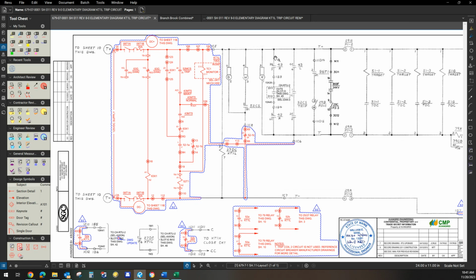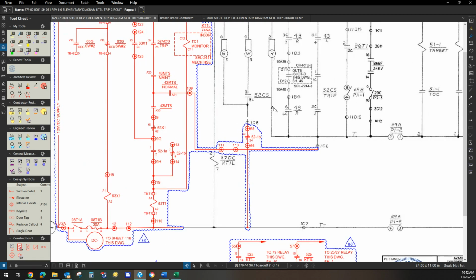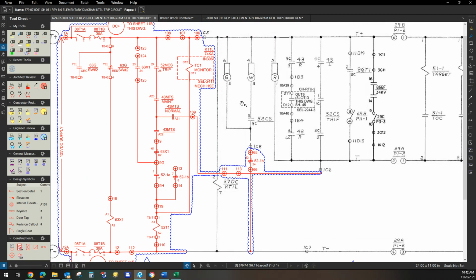It can only flow where there's a path. If you follow this, we'll just start here. You use this real simple example of this green light. The G means green. My water's flowing down. It gets to this point. It goes through this B contact, which is closed. It goes all the way down to my negative rail. So as long as I have water flowing through there, or electrons, this will light up green. Green indicates the breaker is open.